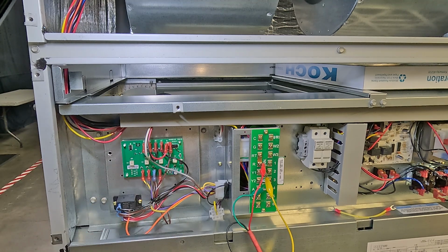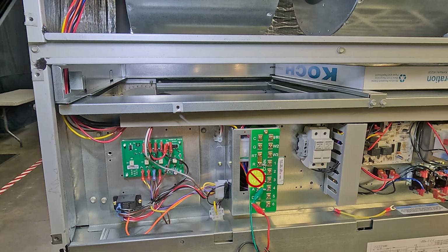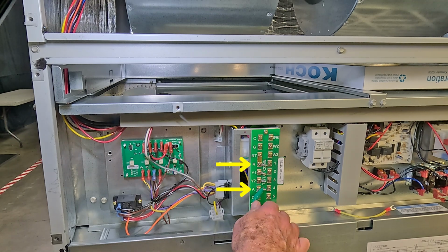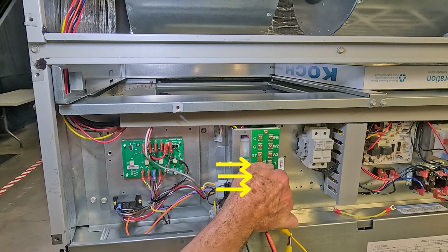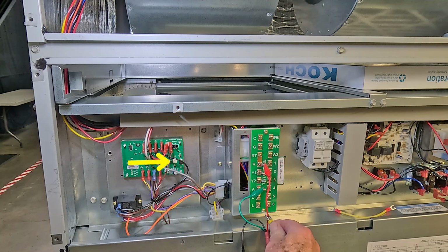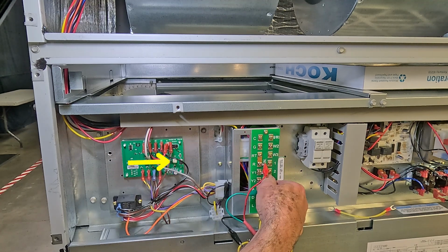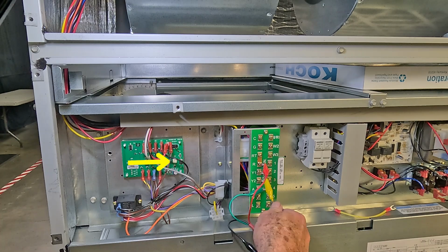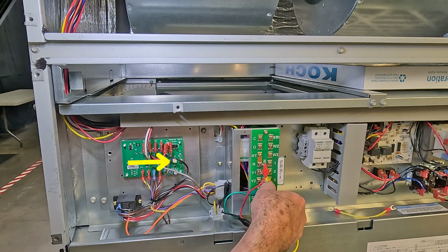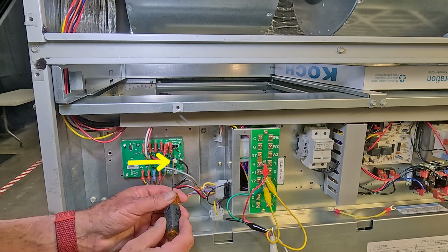This is by design. On a 2-stage compressor unit, there should be no brass jumper between Y1 and Y2. Jumper wire R to A, Y1 and Y2. Turn Y2 pot switch clockwise for the damper to position 6. This will be 450 CFM per the graph.